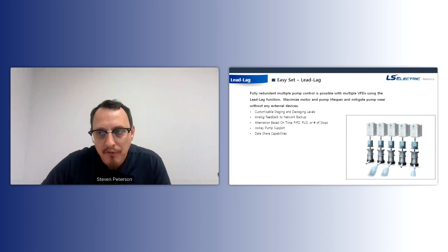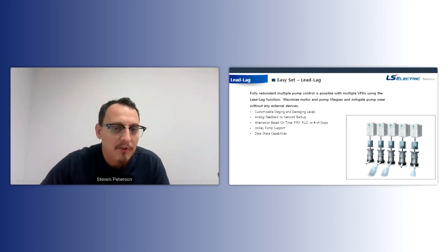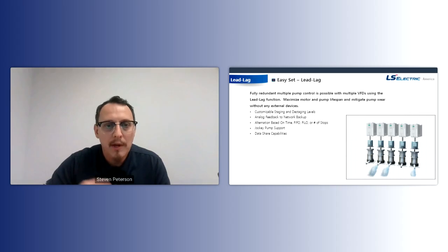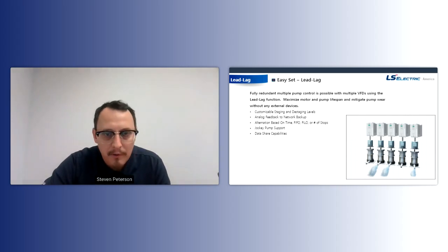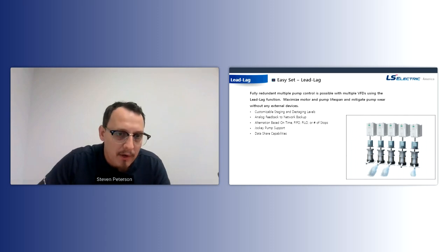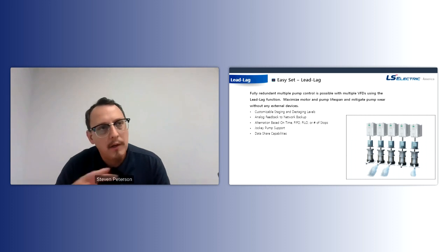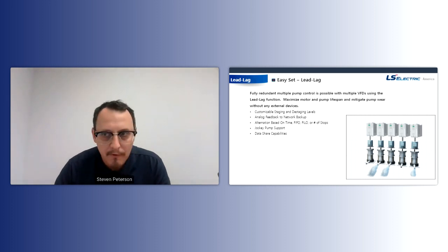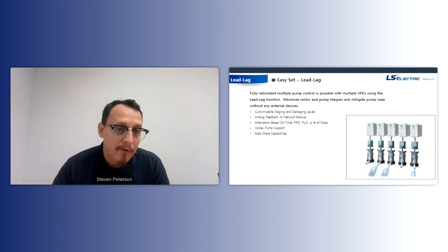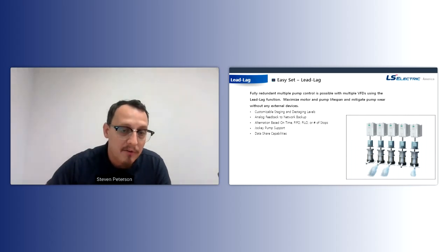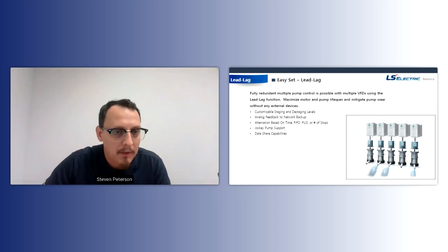Additionally, you could do alternation based on time. You could do alternation based on number of stops. You can do a FIFO, which is a first in, first out operation, or a FILO, which is a first in, last out operation. And we do support jockey pumps. I don't think I have a slide on jockey pumps, but that's like if you have, let's say, 3 pumps, 2 boosters that are 50 horse, and then you have a 5 horsepower smaller one that's a pressure maintenance pump. You could have that 5 horsepower come on first just to maintain pressure, and then the boosters come on as a low priority based on a higher demand time.